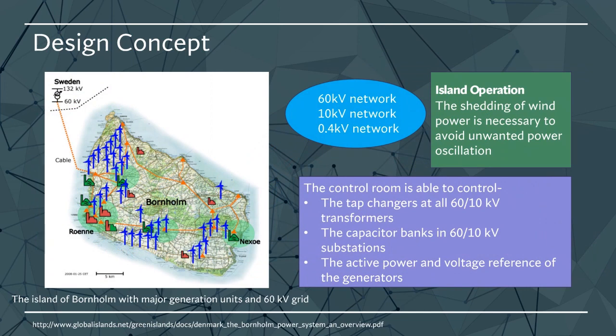Bornholm Island has 3 main networks: 60 kV, 10 kV, and 0.4 kV. The 60 kV side of the transformer in a Sweden substation is connected to the 60 kV substation at Bornholm Island by overhead cables. The control room can control tap changers and capacitor banks in the 60 kV and 10 kV substations. During island operation, shedding of wind power is necessary to avoid unwanted power oscillation in the system.